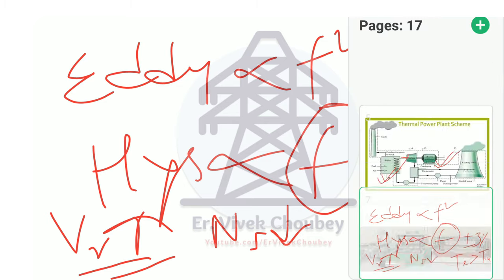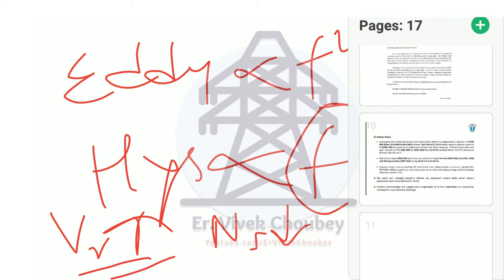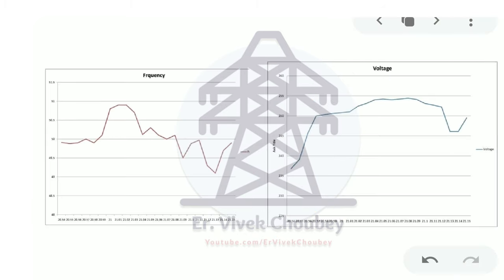Now let me show you the graph of the voltage and frequency. So this is the frequency and voltage graph that you are seeing. As I said, there was a rise in frequency, as you can see here, but you can find that the frequency rise was maintained so well that it did not exceed the plus minus 3% bar. You can see here at 9 p.m. when everyone switched off their lights, that caused the rise in the frequency because of the demand decrease.